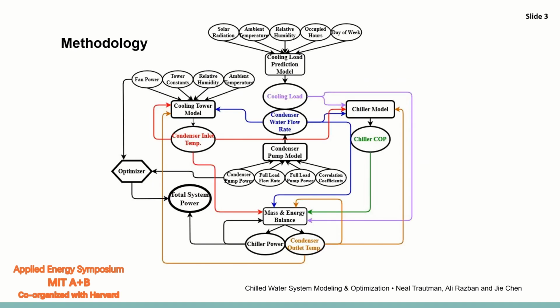So here you can see our overall system model. It's a flowchart of our system model. It's comprised of 5 different component models: the cooling load prediction model, the condenser water pump model, the cooling tower model, the chiller model, and a mass and energy balance, which helps link all of them together. The inputs and outputs of each of these models affect the other models, which ends up helping to model the system as a whole. Additionally, we have user-defined inputs for the cooling tower fan and the condenser water pump, which we send through an optimization process in order to minimize the total system power.